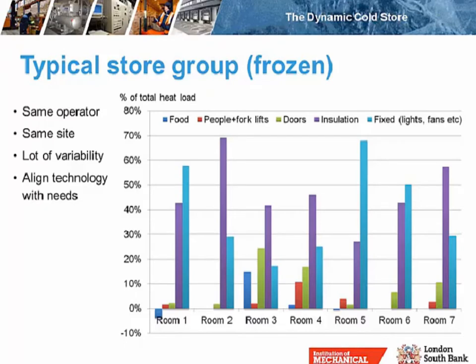In room four, people and forklifts have a reasonably high heat load, so something like automation may have some benefits there, but very little benefit in rooms one or two. In room five, you've got a high heat load from lights and fans, so that room would benefit from LED lights or more efficient fans. Whereas in room three, although it's still a relatively high heat load, it's not the top priority. It's really important to align your technologies with the specific need of that particular store.